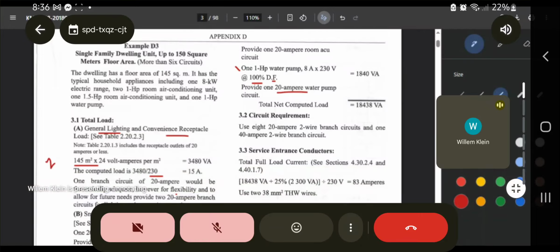So question, 'Di ba po sir, we have a 15 ampere circuit breaker. So why do we use 20, no, when we only have 8 amperes here?' Again, our motors like this one have high starting current. So sometimes there will be times that when you start your motor, it will reach more than 15 amperes just because of the starting. So to prevent your circuit breaker tripping, no, because it might think it's an overcurrent, you'd use 20 amperes. So that's mentioned already in the standard.